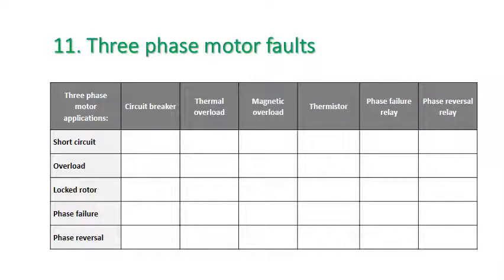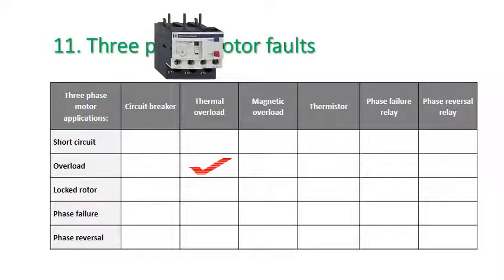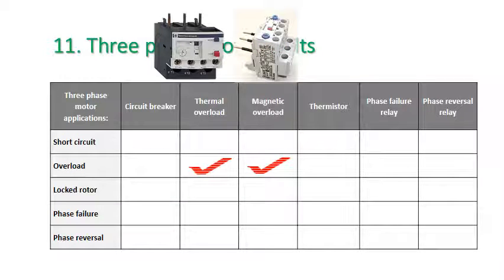So now we're going to look at overloads and what we would choose to protect a motor from overloads, and the first one would be thermal overloads, of course, made to do the job with its 3 bimetals. Then the magnetic overload, which monitors the current with the coils and uses magnetism to trip if there's an overload. Then there is a third choice, which is thermistors. Thermistors don't monitor current, but they do monitor the temperature of a winding in the motor. So if there is an overload, the windings are going to get hot. If the motor's working too hard, then the thermistor will notice that and send a signal to the control equipment to shut that motor down.